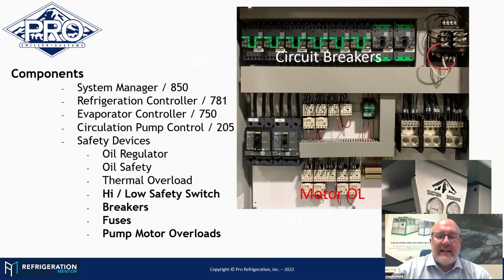We also have the high-low pressure safety switches that are monitoring suction and discharge pressure. On our systems, we mount those directly behind some suction and discharge pressure gauges, just some analog gauges we leave. Those gauges are not consistently calibrated. They go through shipping. It's a tool that we add to the equipment to help make diagnostics a little better. If I was trying to test the accuracy of a pressure transducer, I wouldn't rely on those gauges. I would rely on my own set of transcritical CO2 refrigeration gauges that I service equipment with to get some verification. And I totally agree with that.